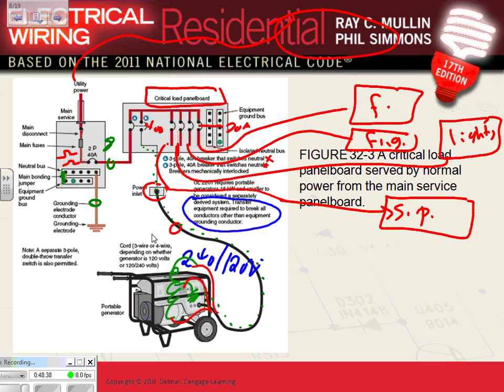This cable is going to have a grounding conductor that's eventually tied to the grounding here and going all the way back to this ground. Can you guys see that the frame of the generator is grounded through the grounding bar in the critical panel, which in return is grounded through the main panel through either the conduit or an equipment grounding conductor? And that's okay for portable generators. If it's fixed in place, we do it slightly different. Fixed in place. Any questions, guys, about this?